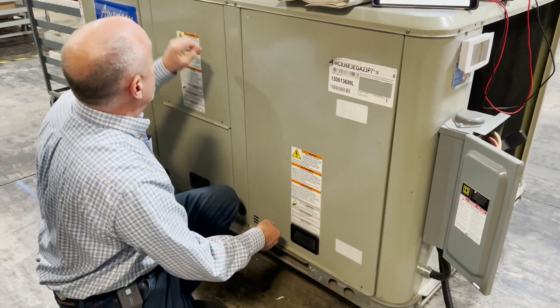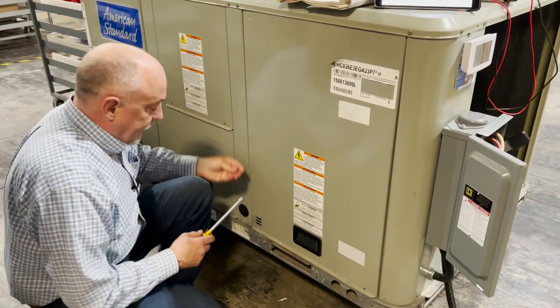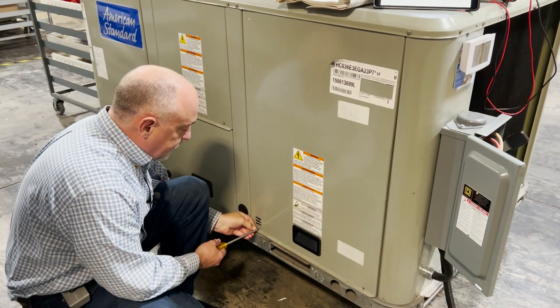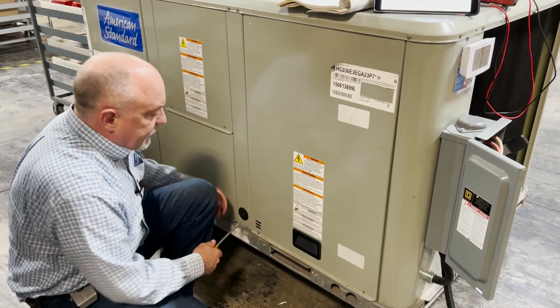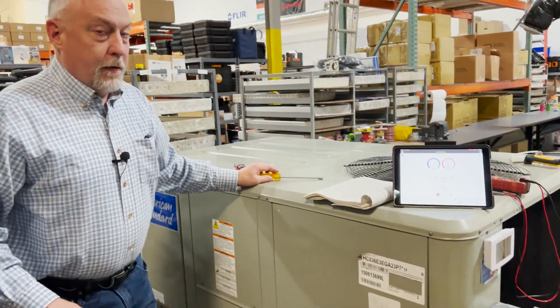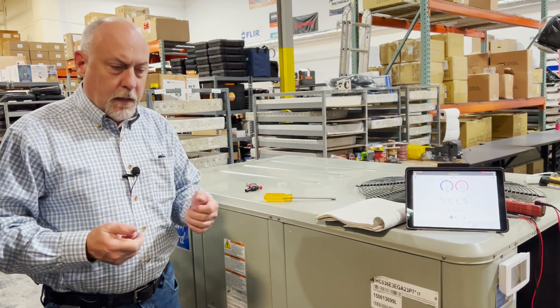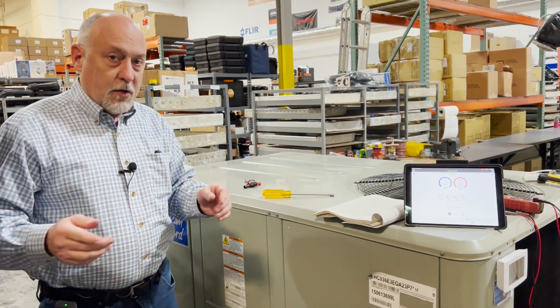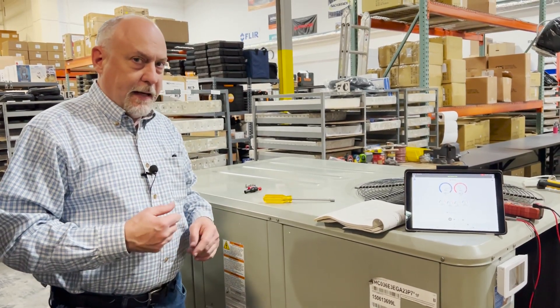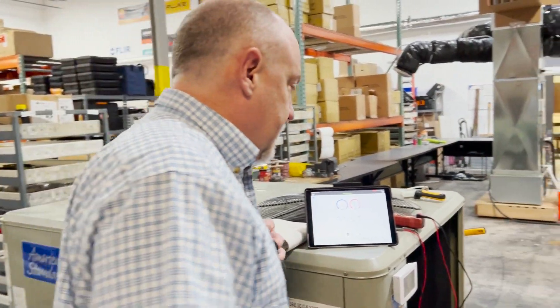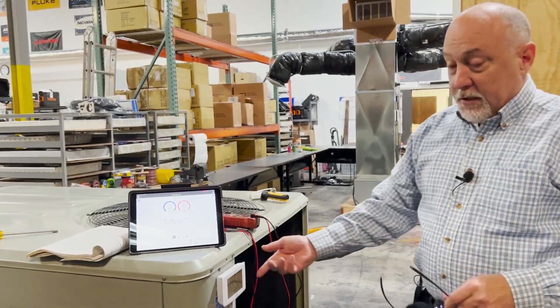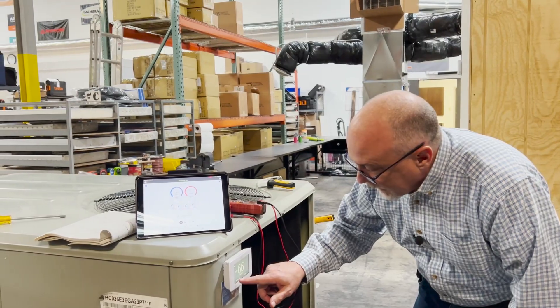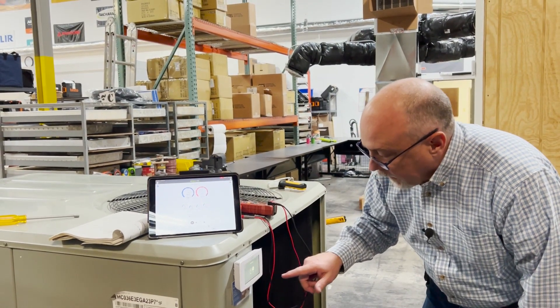Now, a lot of people say, how are you going to make electrical measurements when you have the door on the unit? And that's pretty simple. We're just going to do it through the disconnect. Now, you could run this out. If I was doing this on a job site, I would just disconnect the thermostat and either use just an extension of thermostat wire or something so I could run it out and do what I'm doing here. On this unit here, I've got a stat here so we can actually just test it with a thermostat. I know you don't have the convenience to have your own thermostat hooked up, but for me, I've got it here. So the first thing I'm going to do is just turn my fan to on.